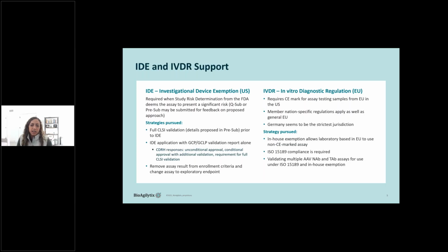All right, let's take a look at our strategies for IDE in the US. Essentially, for a medical device, a study undergoes a significant risk determination. This considers the assay either non-significant risk or significant risk, which then is classified into a designated class.